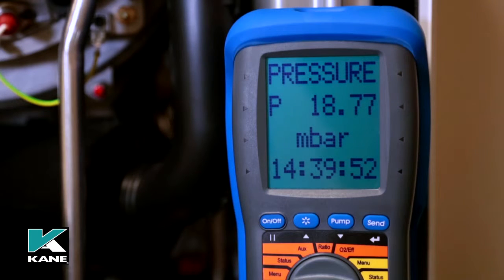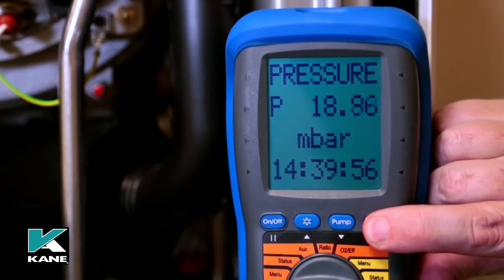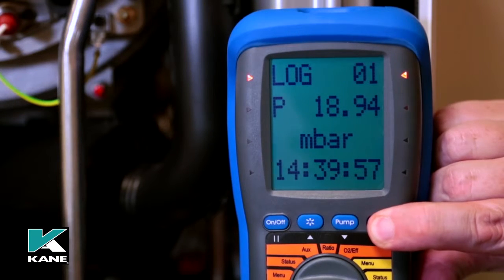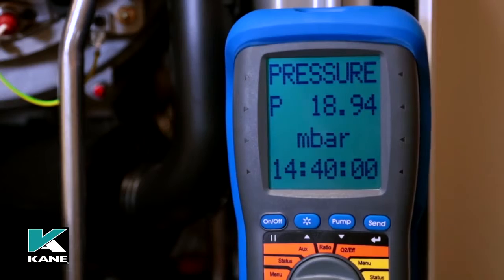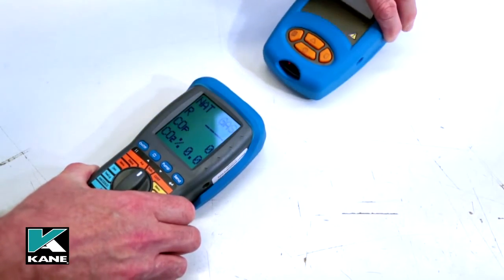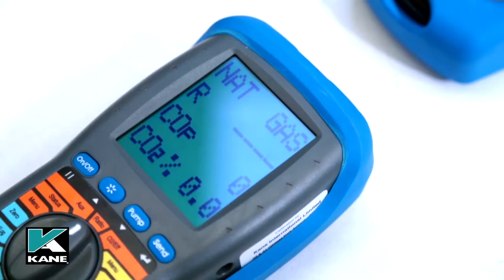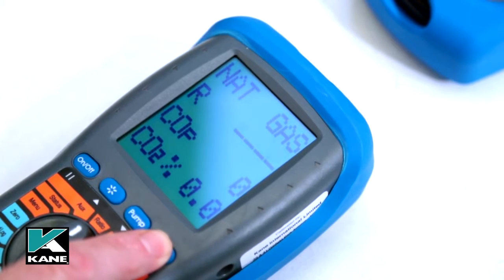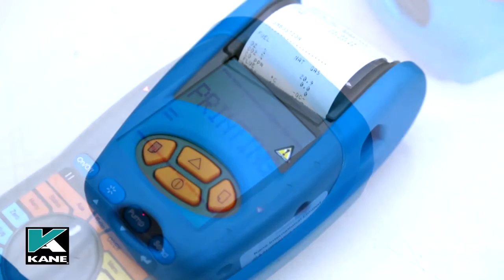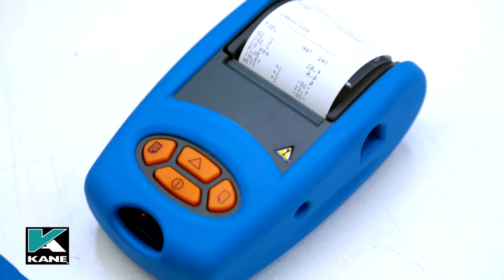The readings can now be stored in the internal memory by pressing and holding the send key until a log number appears on the top line. This is now stored for further reference or printing at a later stage. To print a reading, align the printer to the analyzer, make sure the printer is switched on, and a short press of the send key will transmit the readings to the printer.